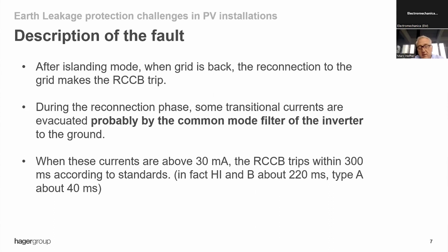These RCCBs are intended to protect people, so they trip when the leakage is above 30 milliamps, and this tripping occurs within 300 milliseconds. This is what is required by the standards. In fact, for high immunity and B-type, having electronic assistance, it's about 220 milliseconds. For a classical type A, with no electronic assistance, the tripping occurs within 40 milliseconds.